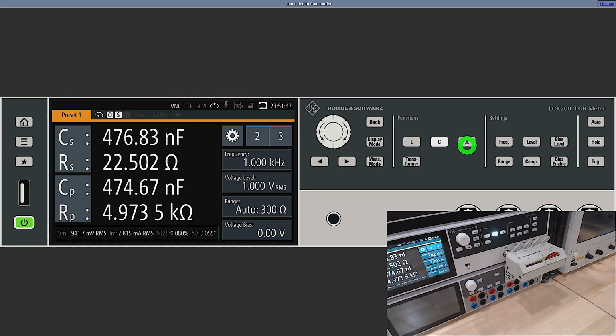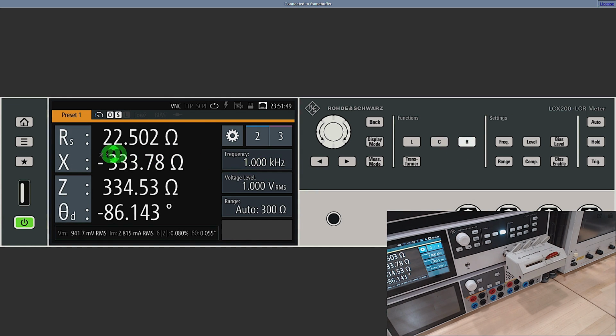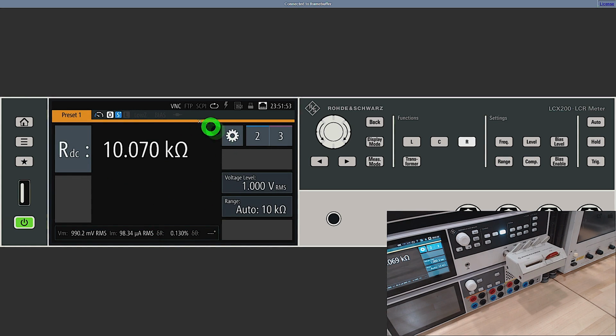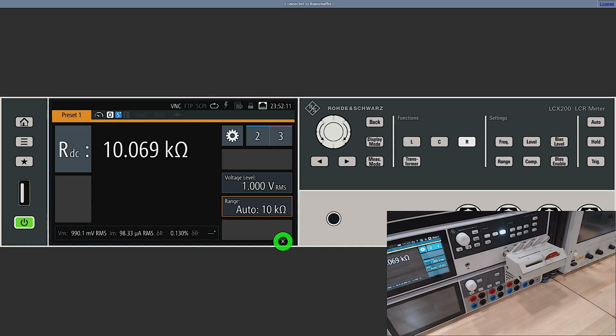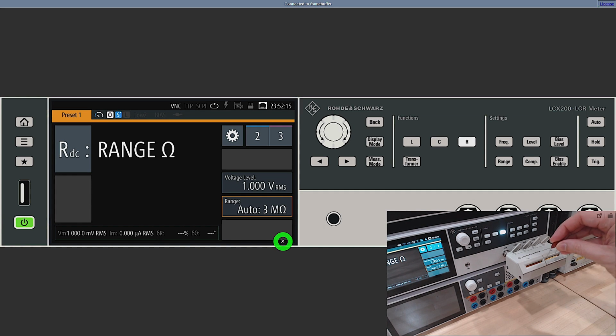So we do have a resistor measurement capability. I can select that and I can go and choose RDC. Now look at that. What do I get? 10 kilo ohm, which is exactly the resistor I added. So in one instrument, I'm measuring the equivalent models, but I also have an opportunity of measuring the leakage within reason, of course, because we do have a measurement range here that once you go over this, you won't be able to measure it. And just to prove that point, I can go ahead and put the original capacitor back in there that has a very, very high leakage parameter. Let's go over there and plug this in. And you can see that it cannot find it.